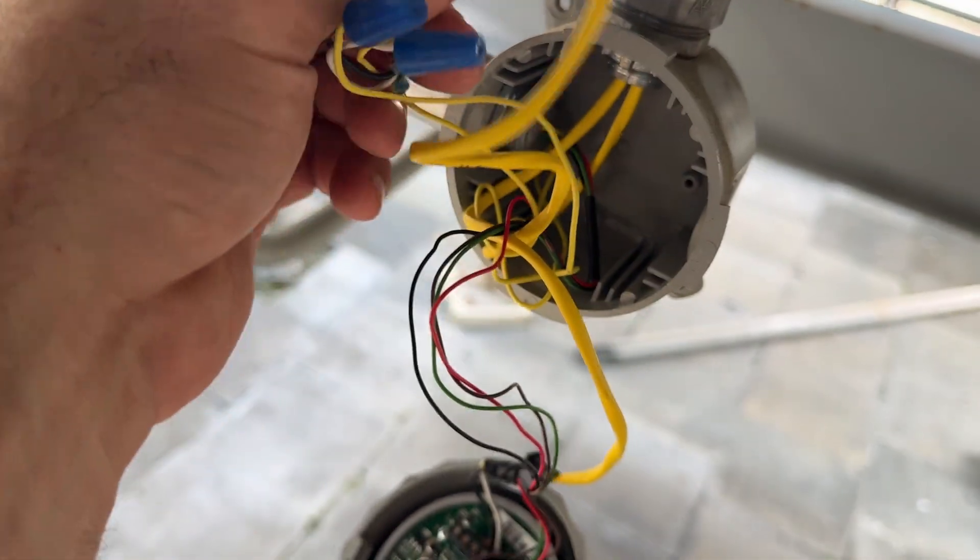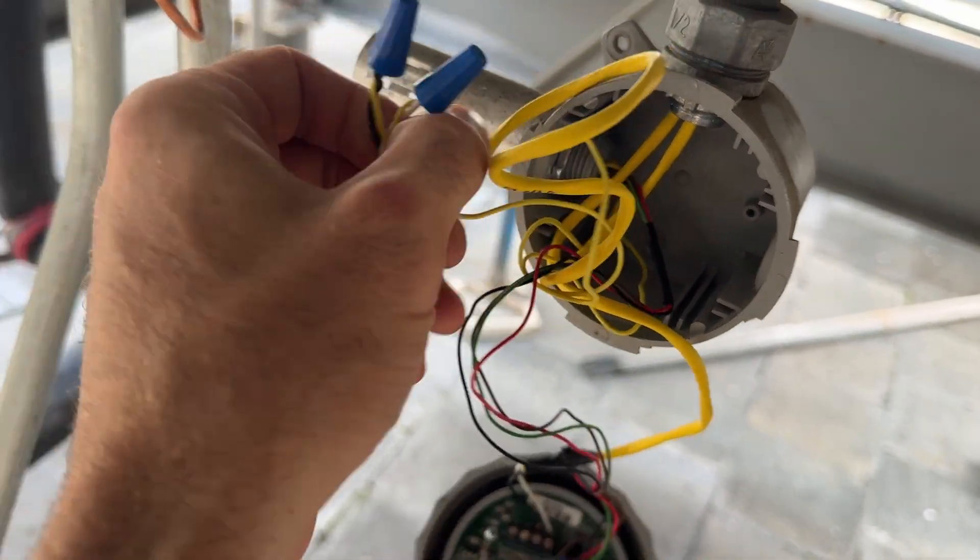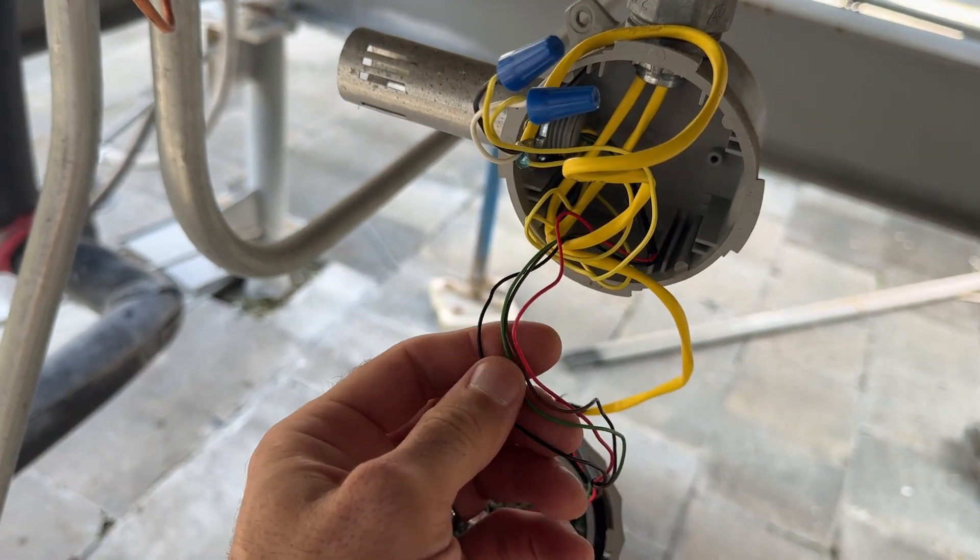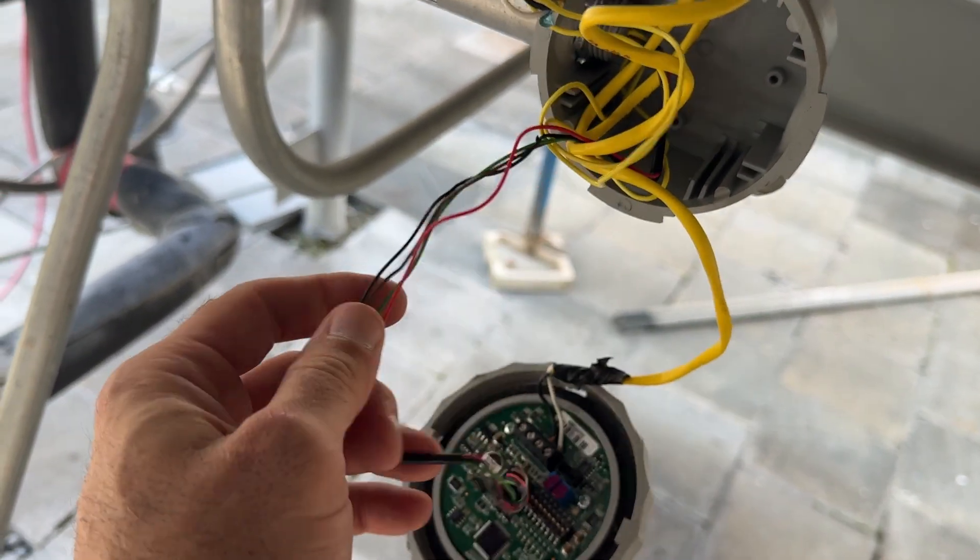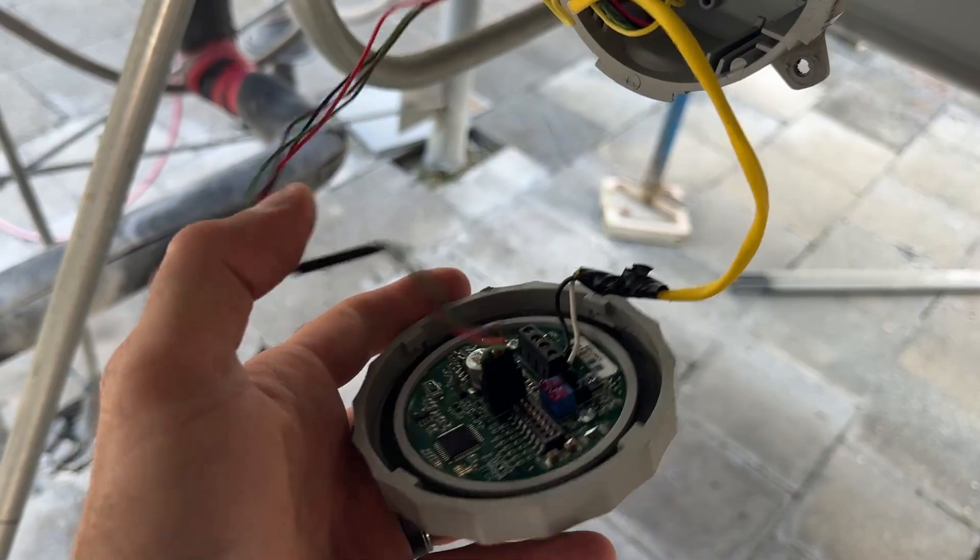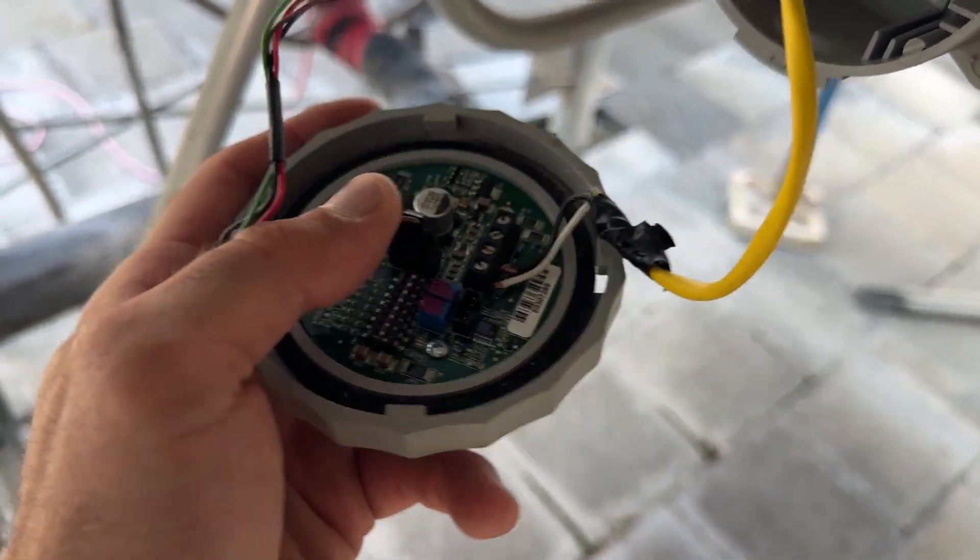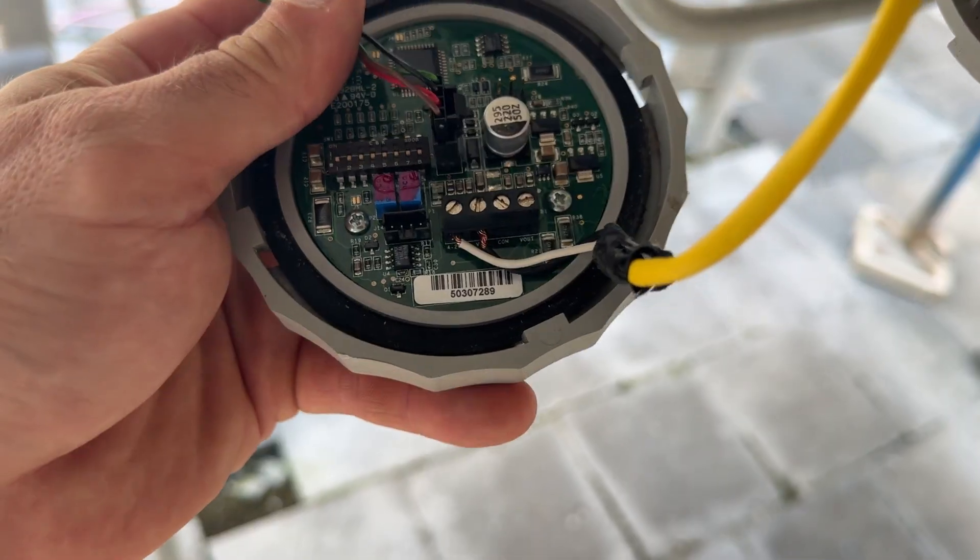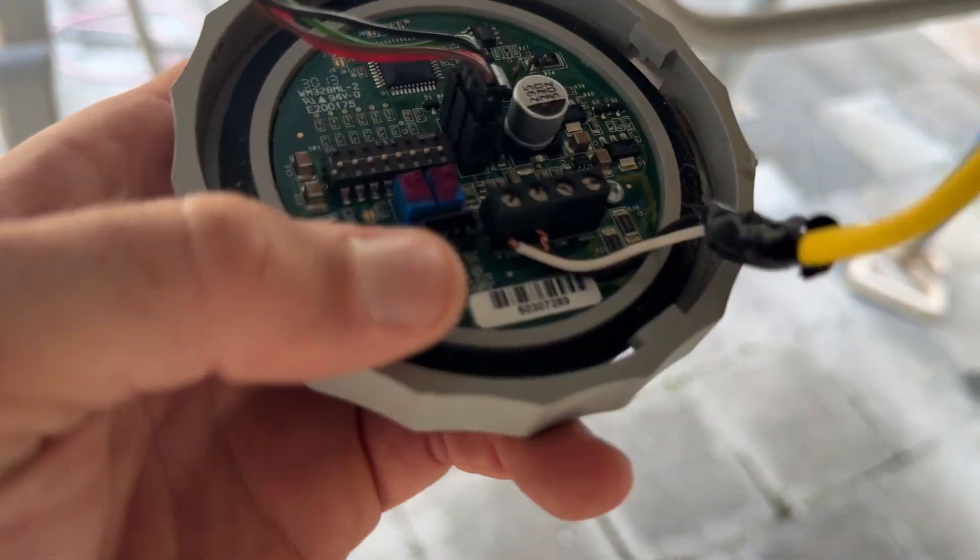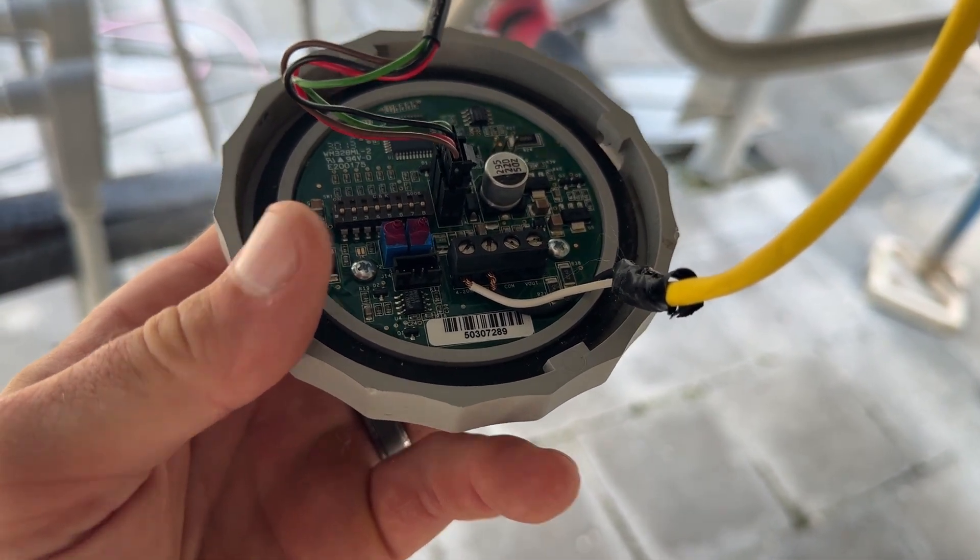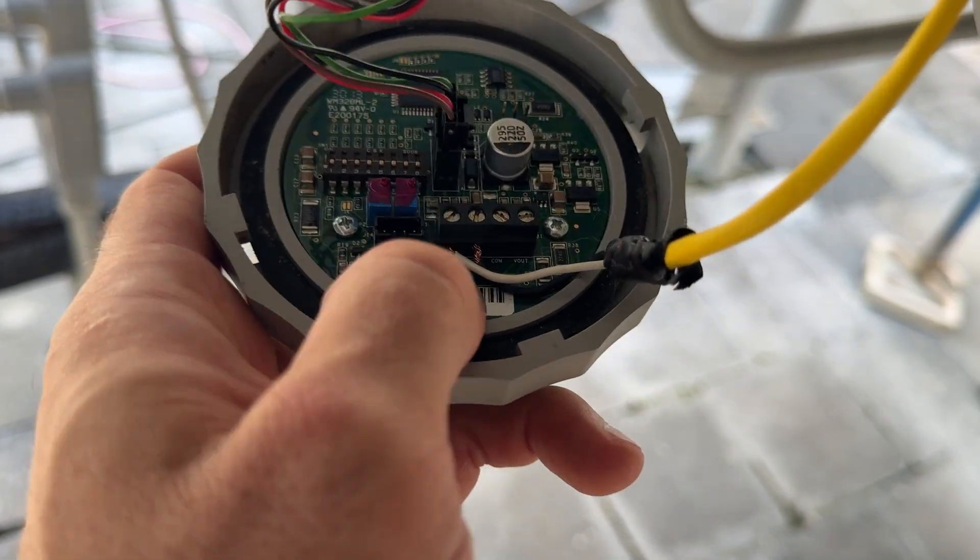And this is the temperature probe that's in there. And we've got this four-wire humidity sensor coming down to this board, which is going to... Let's see if I can get that in focus. I don't know if you can see that. It says 4 to 20 milliamps.